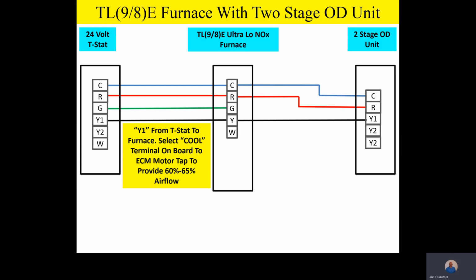And so what we're going to do, we're going to go from Y1 on the thermostat to the furnace and select the cool terminal on the board down to the ECM motor speed taps and select the motor speed that's going to provide 60 to 65% airflow on a Y1/Y call.